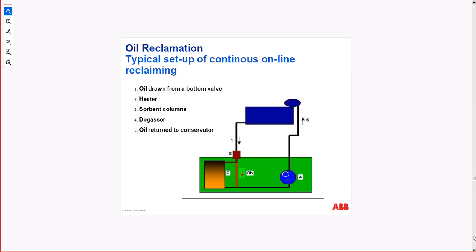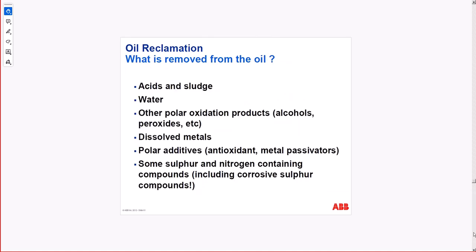Here is the actual block diagram for the reclamation. You have the truck with all the filters and everything, absorbent columns, degasser, and return to the conservator, which is the top tank on the transformer. Oil reclamation, acid sludge. Those sludges that are developed in the oil are actually acidic. They corrode, they clog the tubes, and also they are very good electrical conductors, so they form partial discharge and arcing inside the oil. So you want to get rid of that.